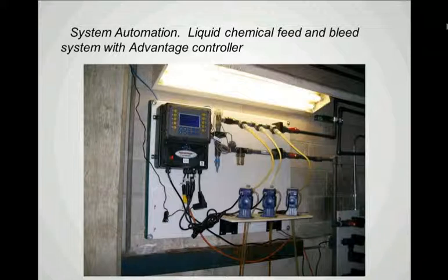And that controller monitors and does this automatically, so it minimizes operator involvement, and it also makes sure that the cycles of concentration are maintained at the desired set point, and that our chemical dosages are maintained within our recommended dosages by automating the feeding of the chemical via the chemical metering pumps.